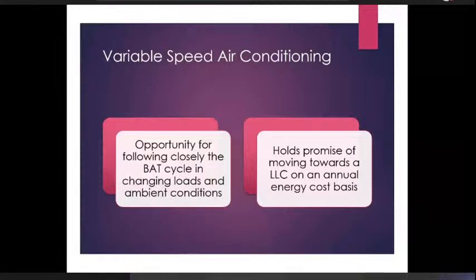Same heat exchanger, same compressor, but with technology to vary the speed, will allow the heat exchangers to be better utilized. There will be no off cycle. There will only be part load and full load. And the part load will far exceed maybe something like 70% of the time, or even, well, actually, if we do the right design calculations for sizing the unit, then 98% of the time the unit will operate at part load. And then what part load will vary. So 95% how much, and 50% how much, and 10% how much is going to be a separate discussion based on the weather and the load conditions. But it is for sure going to lead to this opportunity to save energy costs.